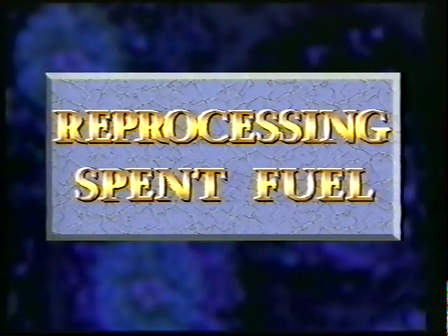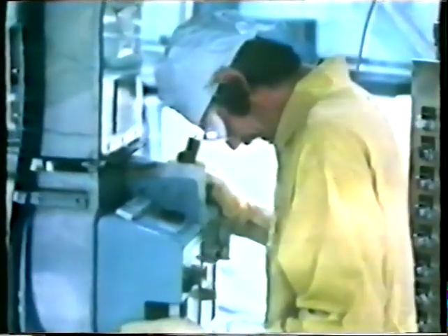In this section, we'll go back to fission and look at the reprocessing of uranium after it has been used. Once the fuel rods have been in use for 1.5 to 4 years, fission products gradually build up and absorb the neutrons, slowing down the reaction. The spent fuel assembly is lifted from the core through a channel to the spent fuel pool. 3 meters of water is enough to prevent radiation reaching the people above.